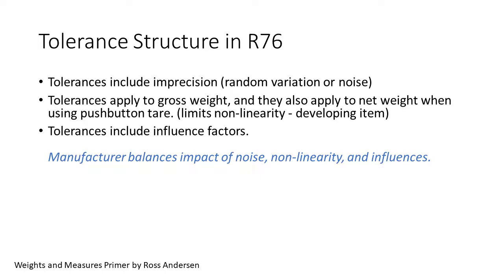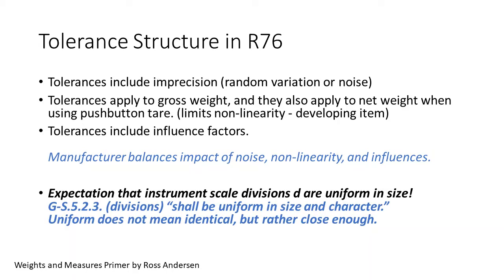Tolerances in R76 reflect that the performance may only be quasi-linear over the weighing range. The R76 tolerances address many sources of error. Tolerances include imprecision or noise. If the instrument gives varying results when tests are repeated, then all of the values must fall within the tolerance. We apply tolerances to both gross and net weight. This limits any curvature or erratic changes in the instrument performance. This is another developing item not included in the charge of the task group. From any net zero indication, the tolerance structure is reset to a new zero reference. Tolerances include influence factors, where the instrument performance changes based on the environment. With these three competing sources of variability, we see that the manufacturer has to balance the impact of all three in combination. An increase in one requires a decrease in the other two. Finally, there's a fourth item. We expect the divisions of the instrument scale to be uniform in size and character. That's resolution.